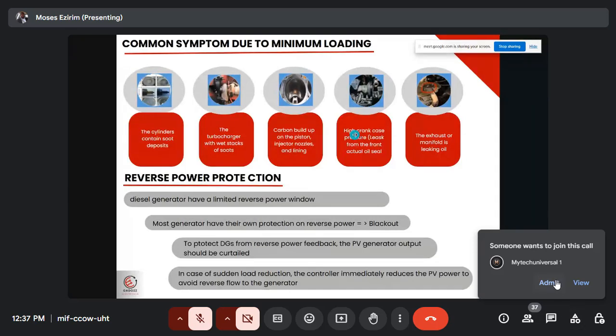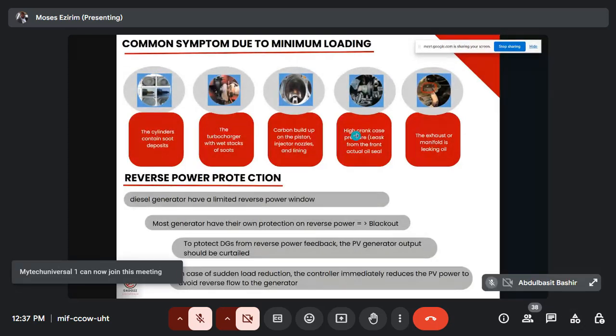Now, these are the symptoms if you run the generator below its minimum for an extended period of time. What will happen? The cylinders will contain soot deposits. The turbocharger will have wet stacks of soot. Carbon will build up in the piston, injector nozzle, and lining. We are going to have high crankcase pressure, and the exhaust manifold will leak. So if you have a PV diesel system and you are experiencing this in your generator, note that it is because the generator has been running below its minimum loading for a long period of time.